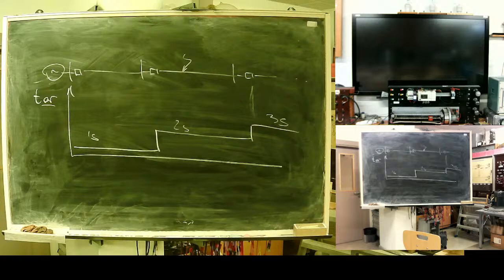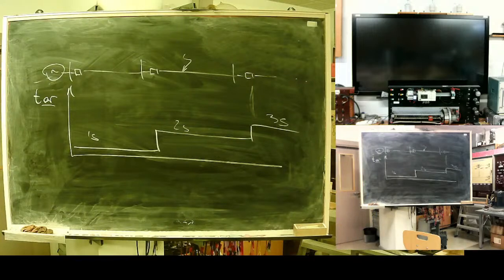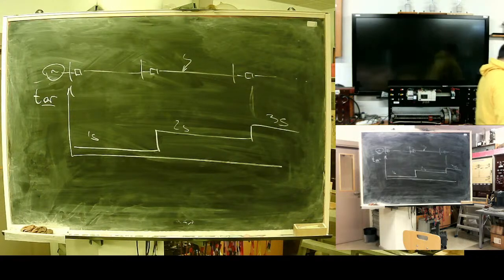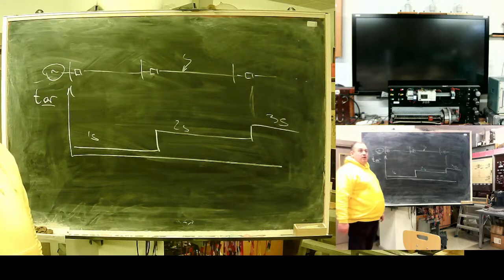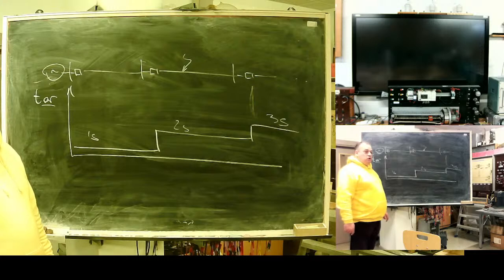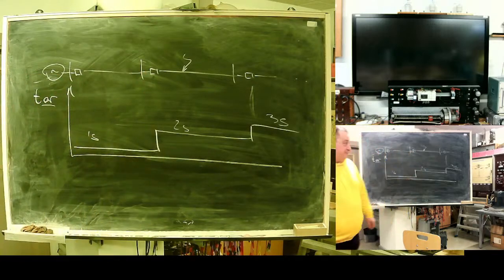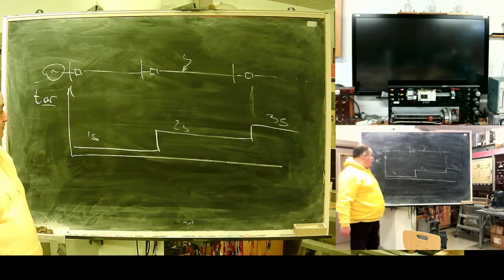Spring recharge. Switch on. Some switches need power to reconnect. This one, good models have enough energy in their springs, but cheaper models can only disconnect and wait. They will not operate until the bus voltage arrives. It's also possible to drive it this way from the power source.